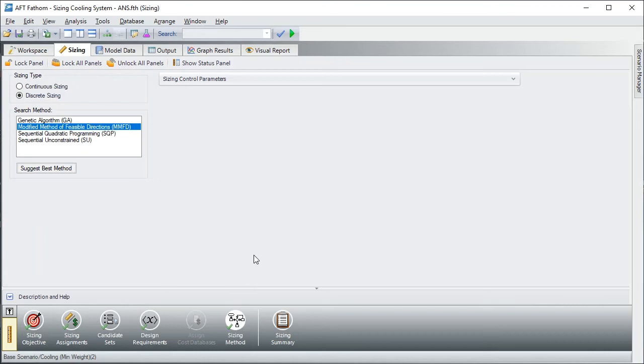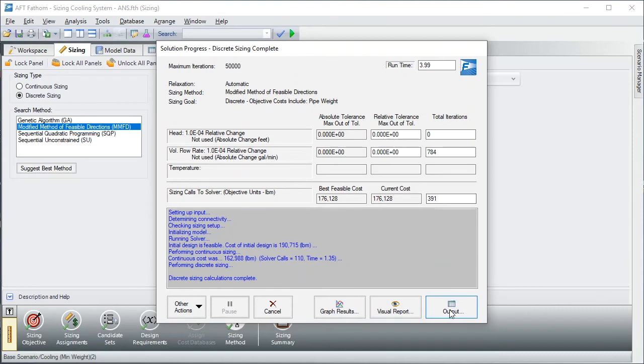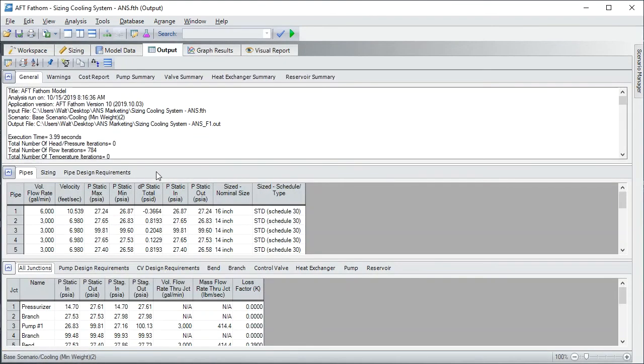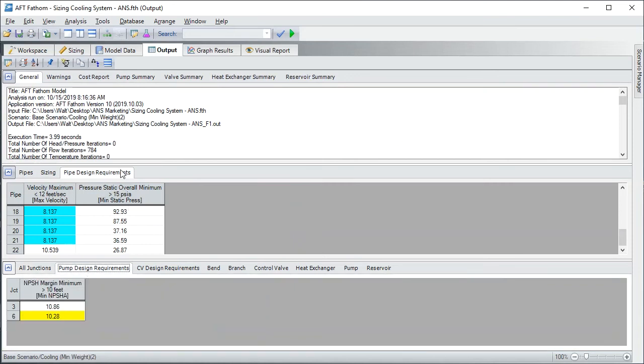That's going to drive our design. The last step is to choose our sizing method. I've chosen discrete sizing because I only want to size for commercially available sizes — which makes sense and is probably what you'd want to do too. Run the model. In a matter of seconds, we've run through hundreds of designs and come up with the best one that meets all of our design requirements for the pipe, pump, and control valve.